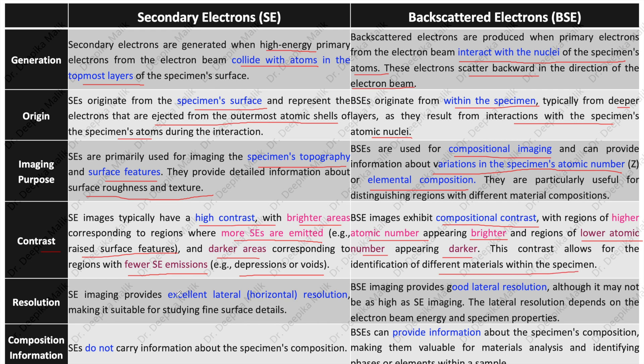Secondary electron imaging provides excellent lateral resolution, making it suitable for studying fine surface details. Backscattered electron imaging provides good lateral resolution, though not as high as secondary electron imaging; the lateral resolution depends on electron beam energy and specimen properties. Secondary electrons do not carry compositional information, whereas backscattered electrons can provide information about the specimen's composition, making them valuable for material analysis and identifying phases or elements within a sample.